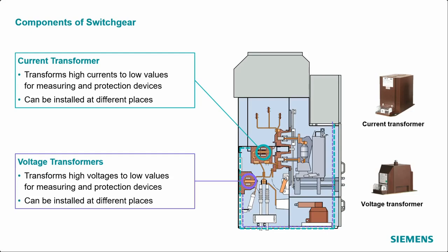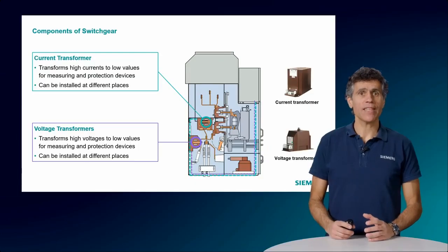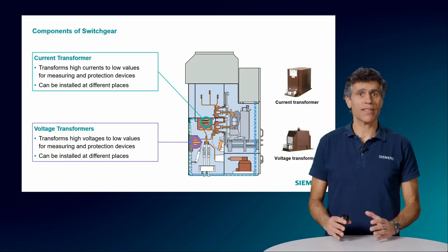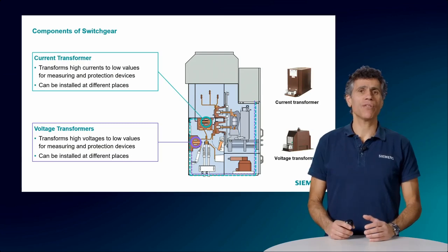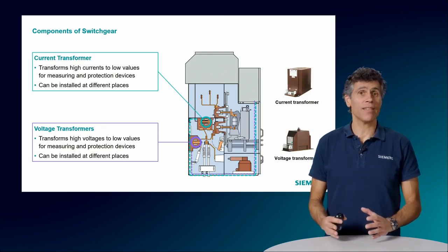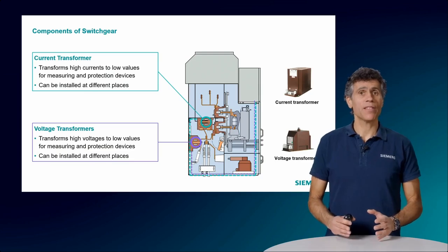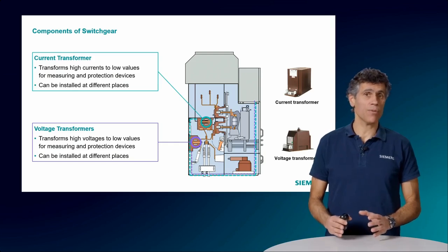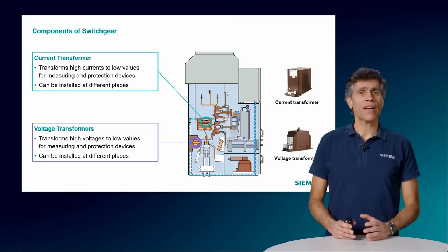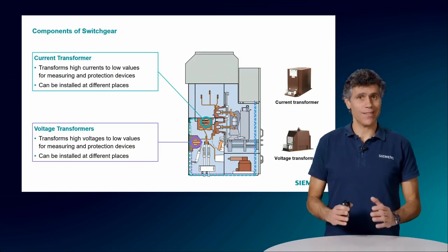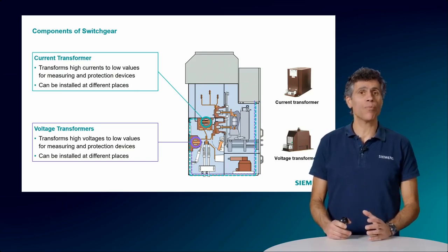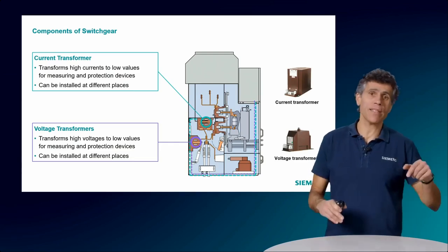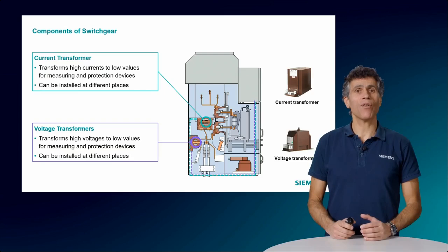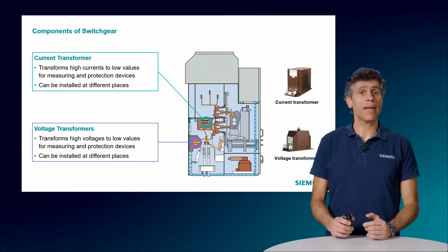Sometimes we want to measure how much energy is consumed, and in that case we need measuring transformers with the correct characteristic for doing precise measurement. Because they are connected to the high voltage, transformers are at the same time insulators and are also, like the main busbar, subject to mechanical stress. And of course, we usually need one for each phase, although sometimes there are exceptions. The current flows through the current transformers in series, and that is why the current transformers have two primary connections, for entering and for leaving the device. The voltage transformers have only one connection because they are connected in parallel.